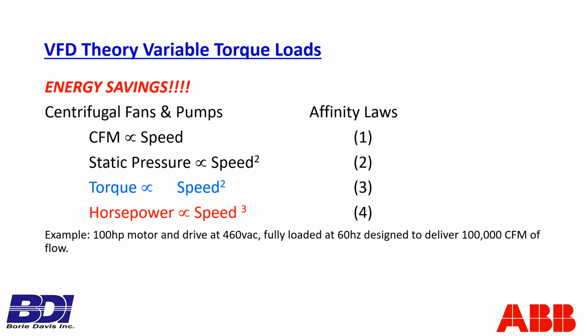Cubic feet per minute of flow, it says, is directly proportional to speed. So the flow rate is proportional to speed. It's the first law, which means I've given an example here, a 100-horse motor with a 460 volt drive, driving the motor at 460 volts, 60 hertz, is designed to deliver 100,000 CFM of flow. If I run at 100% speed, 60 hertz, I'll deliver 100,000 CFM. If I run at 30 hertz, 1/2 speed, I will deliver 50,000 CFM of flow. If I run at 15 hertz, 1/4 speed, I'll deliver 25,000 CFM of flow. If I run at 45 hertz, I'll deliver 75,000 CFM of flow.